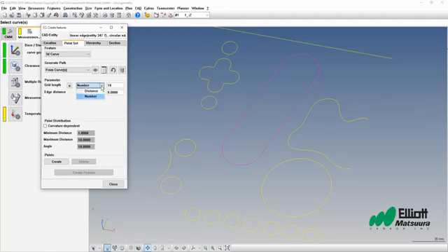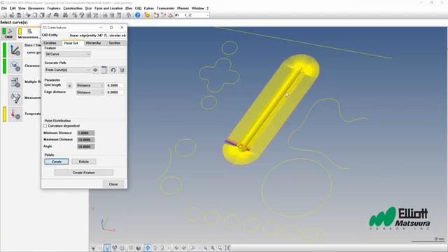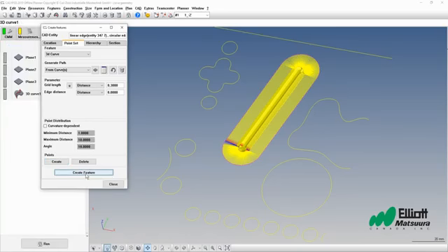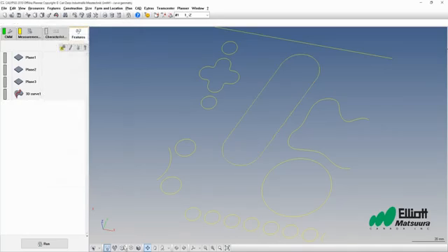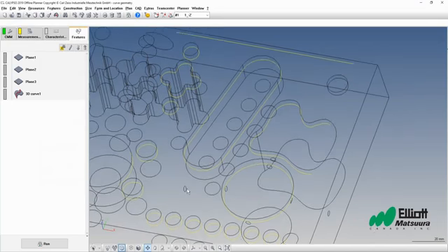And then I'll change this number setting to a distance setting here. I'll apply points every 300 microns. There. That's a very thorough slot measurement. We'll go ahead and create that feature. And now we have a 3D curve in our feature list. We'll restore the CAD model. And now it's time to create a simple circle and a line.